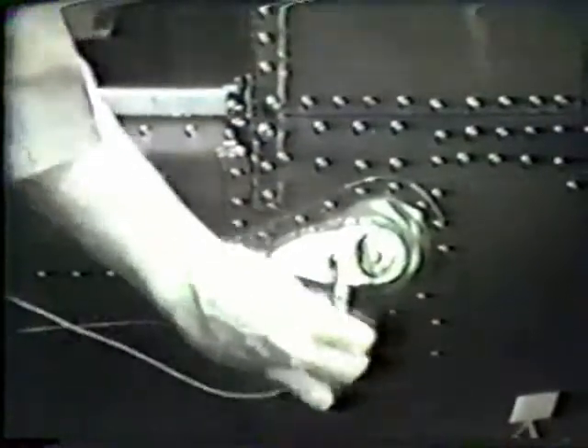Such lights are exposed to the weather, and sockets and their grounds can deteriorate. The socket seems firmly attached. Its ground should be good. The jumper wire will tell us if it really is good. If the socket ground is defective, the light should come on when grounded with the jumper wire. It doesn't. The ground on the socket is okay.